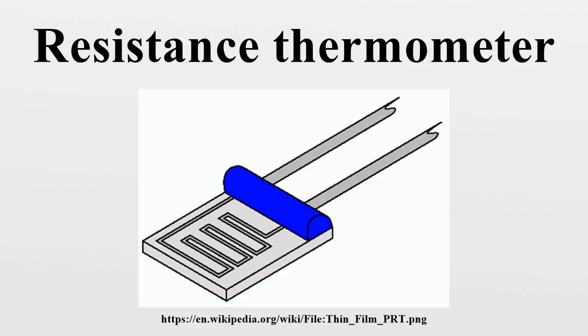The American fundamental interval is 0.00392/°C, based on using a purer grade of platinum than the European standard. The American standard is from the Scientific Apparatus Manufacturers Association, who are no longer in this standards field. As a result, the American standard is hardly the standard even in the US.